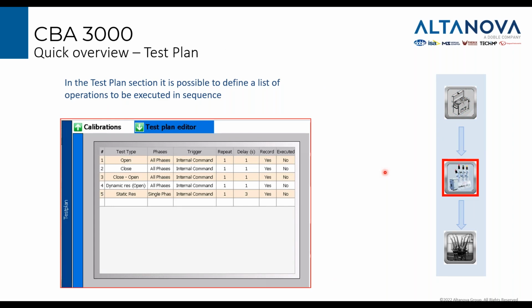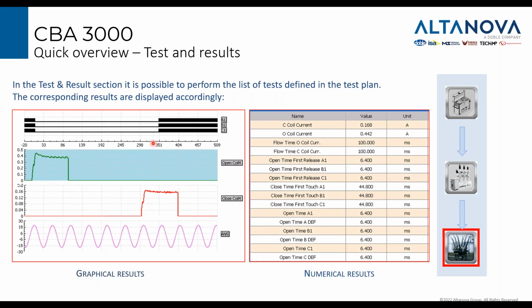Then you decide the list of tests, and this test plan can be saved and executed at a second moment. For example, you can save the test plan and pass the same sequence to your colleagues, so they don't have to make any setting. They just need to open the file that you are passing. In the end, you press the start button and you have your results displayed in a graphical form, but also in a numerical form, because it's very important to have an algorithm that makes all the measurements and calculations for you. Otherwise, you have to make a complex analysis out of this graph. It's very comfortable to have something already prepared for you.